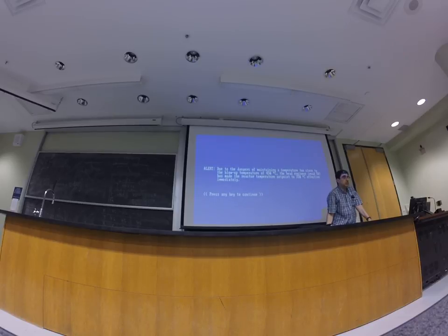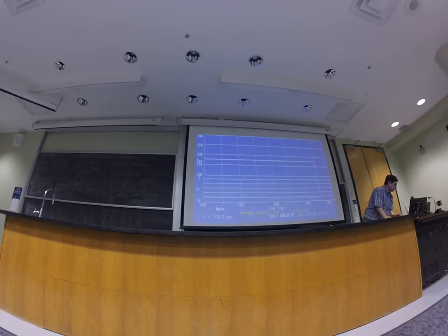When we run the same thing now with PI control, we're going to see it very nicely return to the set point. Here's now the set point change. Correctly, it increased. It's the luck of the draw how close we'll come. Actually, in this case, we came fairly close. Some of you may not come so close.